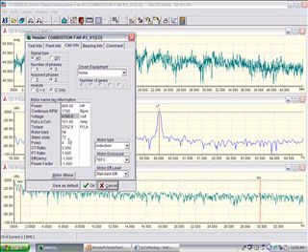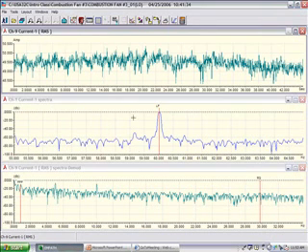I highly recommend, if you are doing this type of analysis, if you are doing electrical signature analysis, that as part of your repair practice, if you have a report coming back from your motor repair facility, that you request the number of rotor bars and stator slots. If you do not go this direction, and you have a vibration program in place, you still want to know the number of rotor bars and stator slots. A lot of what we're looking at here is very similar to what a vibration analyst looks at. Okay? So I'm going to focus in here.